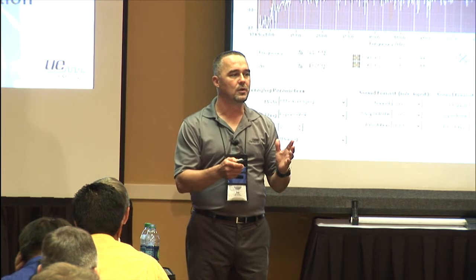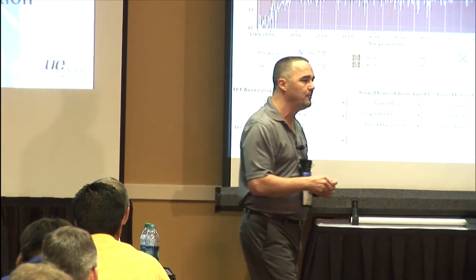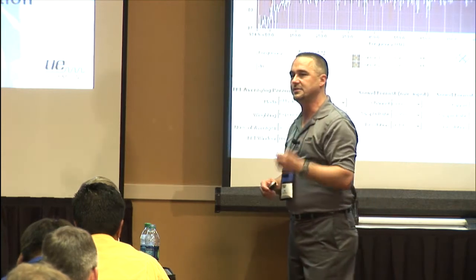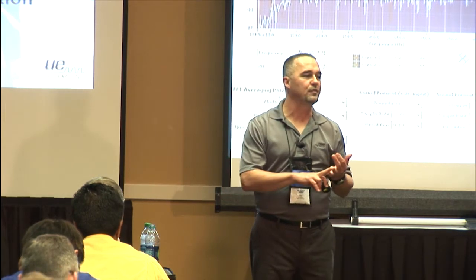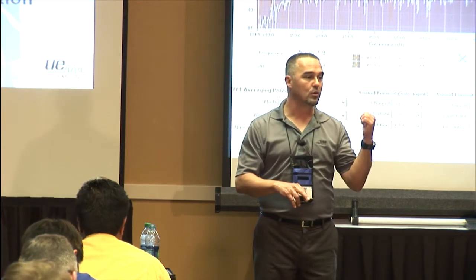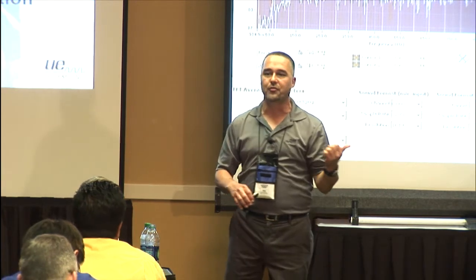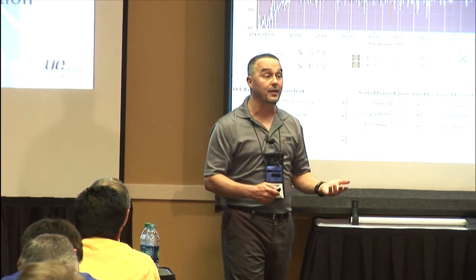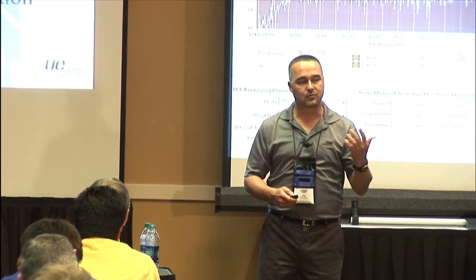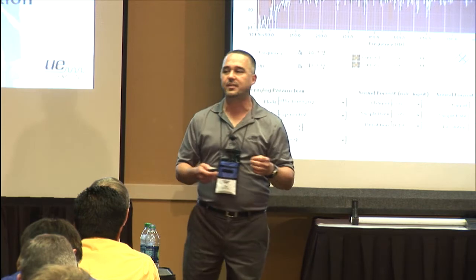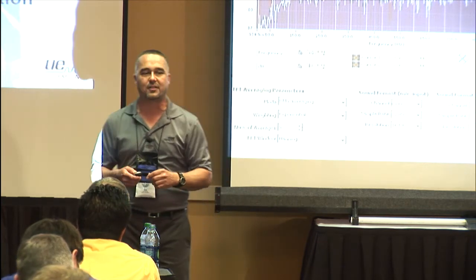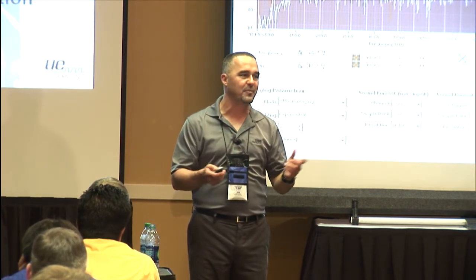Comparing the two, we always tell our guys if you use just the FFT, you're going to miss things. This tool tells me 2 things: number 1, if it's some type of fault, and number 2, if it's electrical in nature or not. I can rule out electrical or non-electrical type issues - it doesn't tell me what it is, it tells me the nature of it. The frequency noise in between tells me something related to electrical is there, but it doesn't have the spectrum I'd expect if it was tracking or arcing. It's something different in this case.